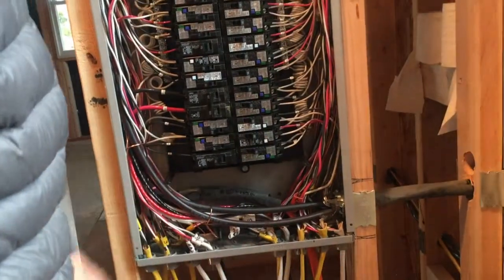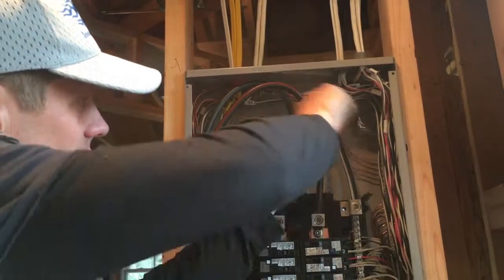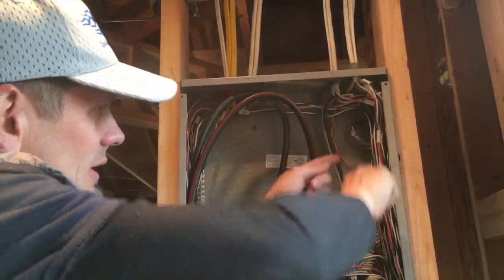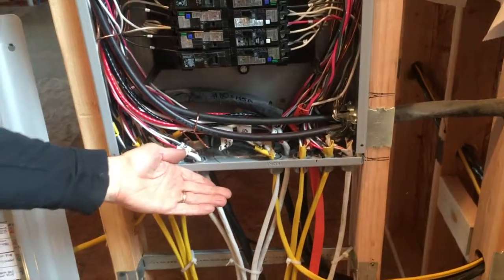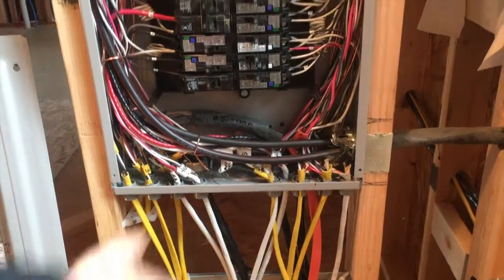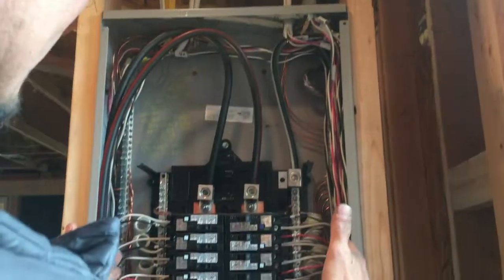The disadvantage is cutting it in when it's cold — right now it's been 48 degrees, and cutting 14-4 is very slow to peel. It's easy to nick the wires on the backside, so you have to be cautious. Whereas with 12-2/2, you can rub it to heat it up, cut it, split it, and it's a lot quicker. Another advantage is you have a lot fewer grounds inside the panel when running multi-conductor cable. I love using these 3M cable stackers up here — they work very, very well.